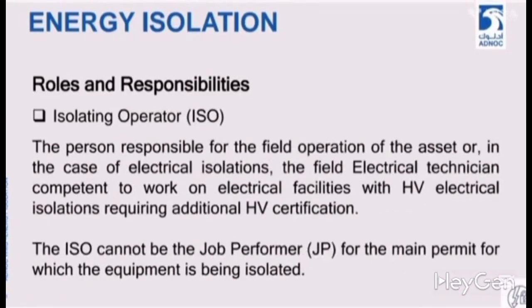What will be the roles and responsibilities of the ISO or isolation operators? The person responsible for field operations, and in case of electrical isolation, the field electrical technician competent to work on electrical shelters with high volt electrical isolation requiring, high volt certificate. Okay, so the isolation operator will be your field operator, your area operator, your permit issuer. It could be your PE from the ISA isolation authority, who is determined with the isolation asset and the cubicle. The responsibility of the ISO is to ensure, verify and rectify all isolations there and to implement them.